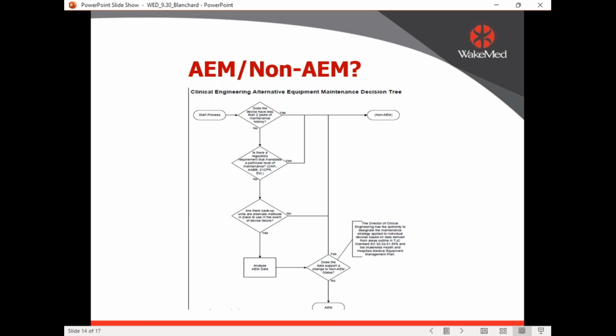So for an AEM, the first question is, does the device have less than 2 years of maintenance history? If we say yes, it has less, then it's non-AEM. We're doing whatever the manufacturer says for those 2 years to gather enough information. But if it's something that we've had for more than 2 years, the next question is, is there a regulatory requirement mandate or a particular level of maintenance? Like CAP, AABB, 21 CFR, all those requirements.